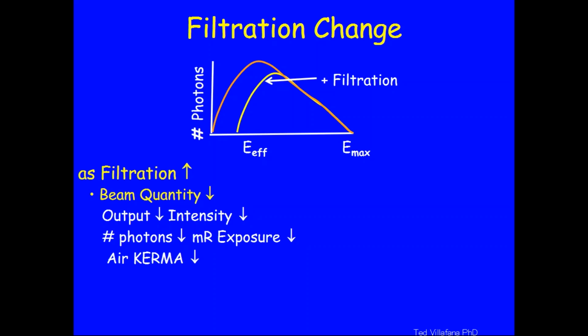They are harder. So in a typical X-ray beam where you have both hard radiation and soft, the soft being the low energies, the hard being the high energies, it's the low energies, the soft radiation, that will be preferentially absorbed in that filter material. Okay, very important idea there: preferential absorption of the low energy components. Now, there's going to be absorption at all energies, but the higher energies will be of relatively lower significance in removal by attenuation. It's mainly at the low energies, as shown by these curves over here.